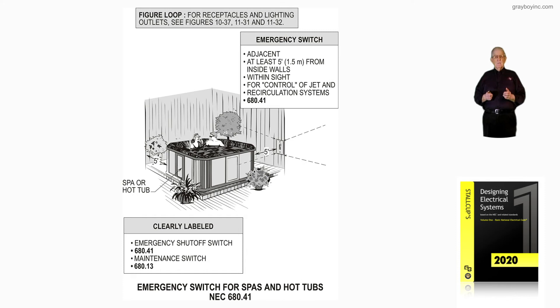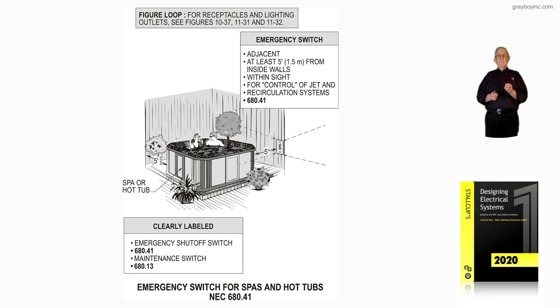The NEC loop again addresses receptacles and lighting fixtures in and around the pool so that you have a constant figure loop. You can see the items that mostly give trouble in and around these pools, SPAs, or hot tubs, whichever you're reviewing. The emergency switch is highlighted here — the boxed-in information states it must be adjacent, located at least five feet from the inside walls of the SPA or hot tub, for control of the jet and recirculating system in accordance with 680.41.